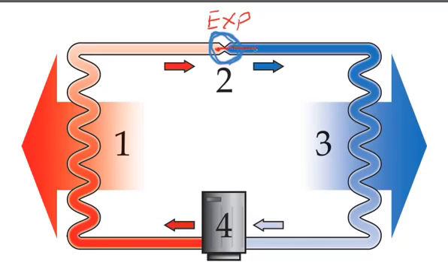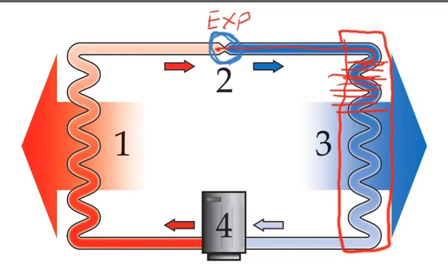This liquid will travel down this copper tube that goes to what's called the evaporator coil. Now, the evaporator coil has aluminum fins that are attached to it, and what that does is helps the heat from the inside air that's blowing over this coil to absorb into the copper or the aluminum fins and the copper tube, and then into the refrigerant gas. So where the evaporator coil gets its name is this liquid enters the coil and evaporates, and by the time it gets to the end of the coil, it's totally evaporated and there's no liquid left in it, and so we have a gas by the time it reaches the end of the evaporator coil.